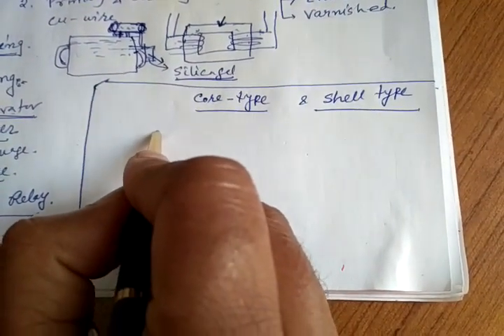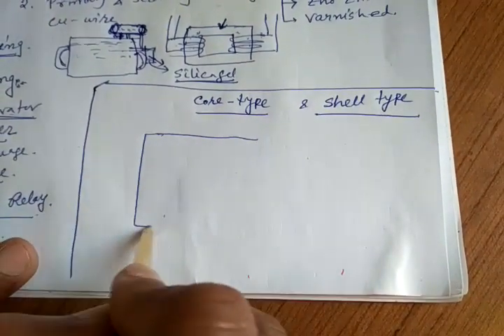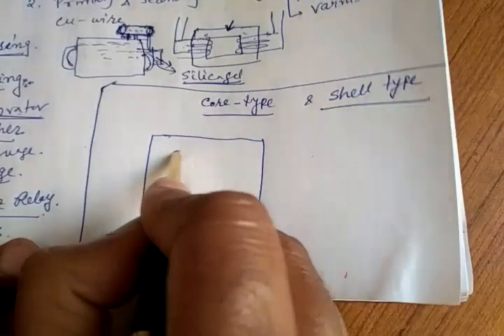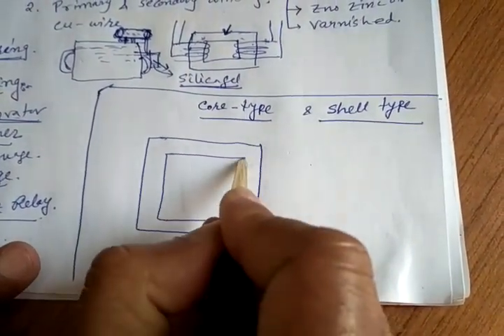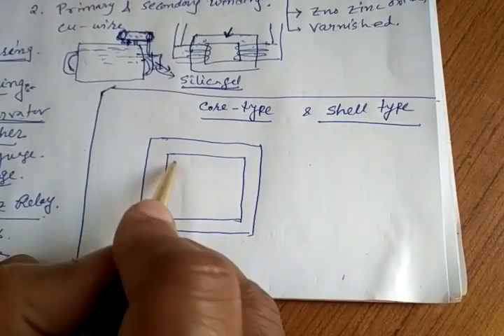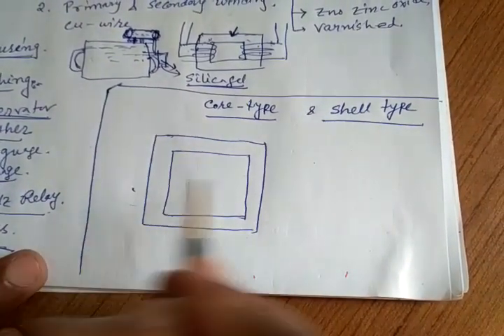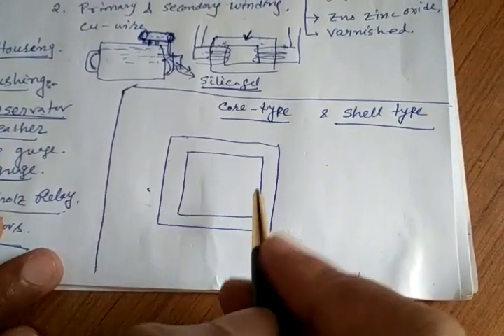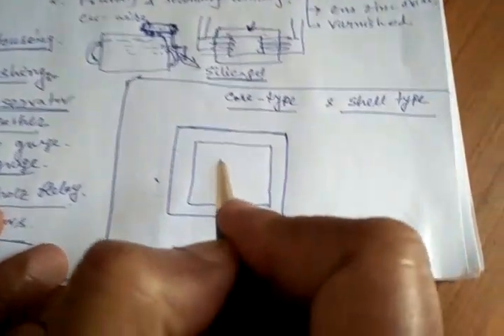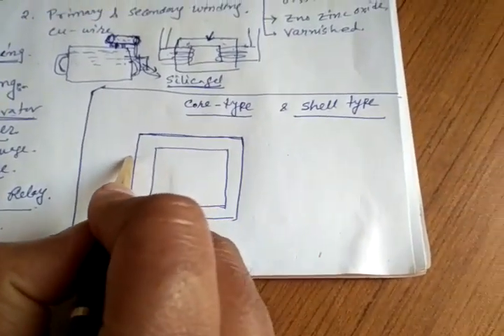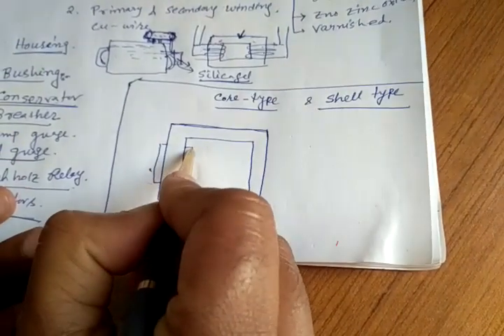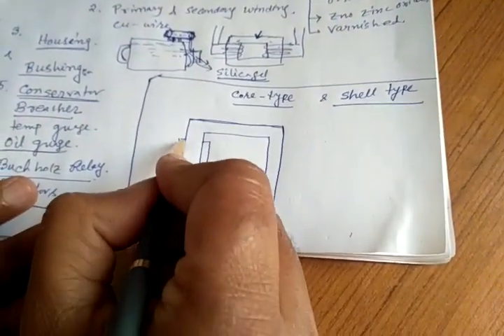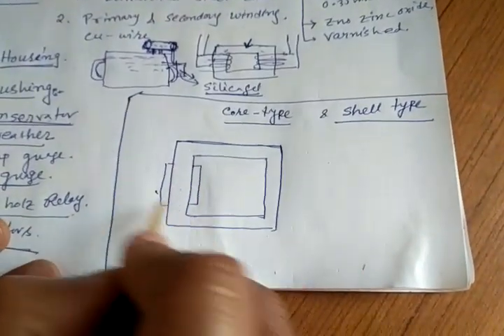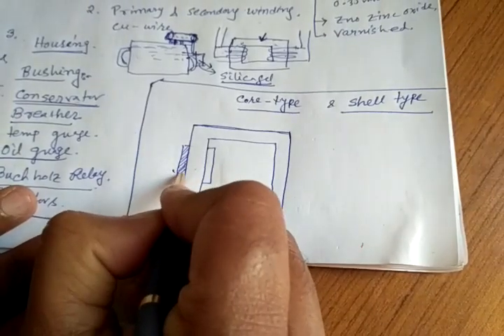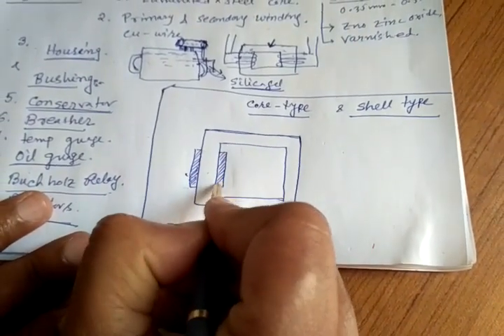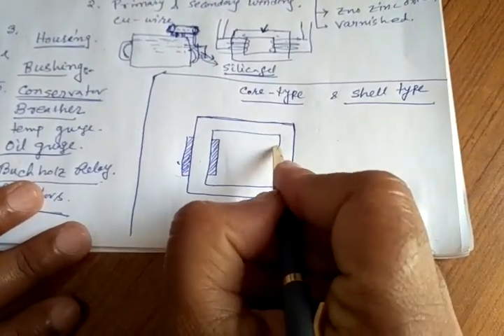In core type, we have already started with core type. So in this core type, what happens? This is the transformer core and windings are wound. Till now we have shown that this is primary and this side is secondary, but practically when transformers are produced, for some practical advantage, both the limbs, this one and this one, contain both primary and secondary winding. Like first few turns of primary winding, or we can say first few turns of low voltage winding, are in both the limbs.